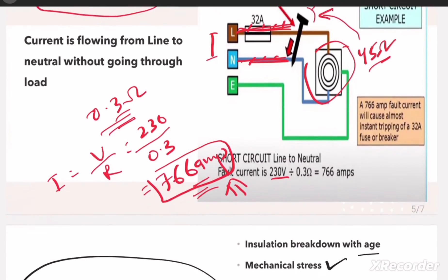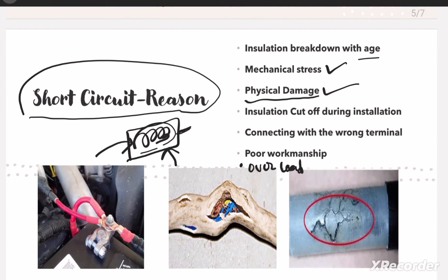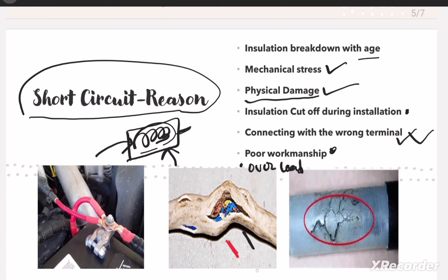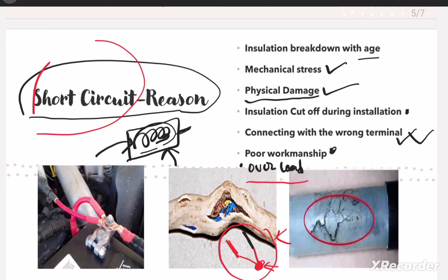Other reasons include poor workmanship during installation, where cable insulation is damaged. Another common reason is wrong connection — for example, if an electrician connects both a neutral wire and a phase wire to a single terminal point, it will cause a short circuit. Also, overload itself is an important reason: when equipment is overloaded for a long time, the insulation degrades rapidly, eventually leading to a short circuit condition.